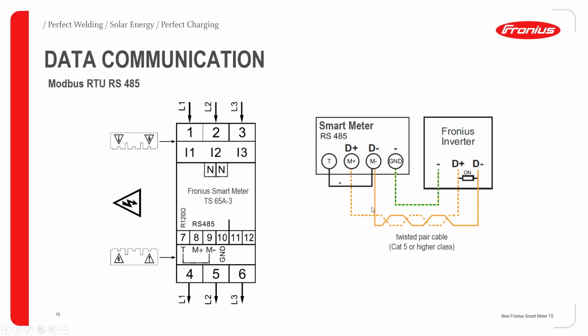So you will be connecting it to the smart meter point. Like here it's numbered as 8, 9, and 10. So M plus, M minus, and the ground, respectively. Always use the twisted pair cable, and please make sure that the cables are at least Cat 5 or higher classes. Yeah, and don't forget the terminal resistance. This is very, very important for the end devices. And please ground the shield of the cable on one side.